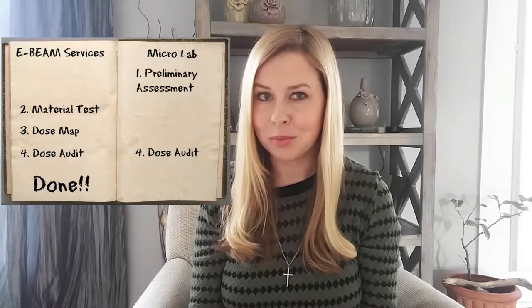Once this sterilization validation is performed, you won't have to do it again unless there's a change to your product or your packaging. Now, often I get asked if customers looking to switch sterilization providers have to redo the validation process. If you're looking to switch methods completely, like gamma or ethylene oxide to E-Beam, then the short answer is yes, you do. But if you are switching from one E-Beam to another, the only step that has to be redone is the dose map.